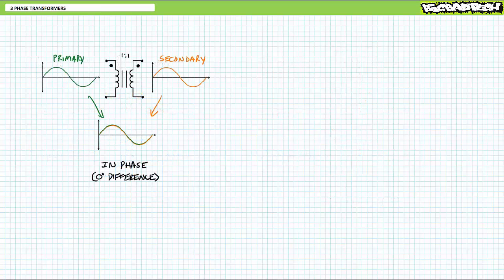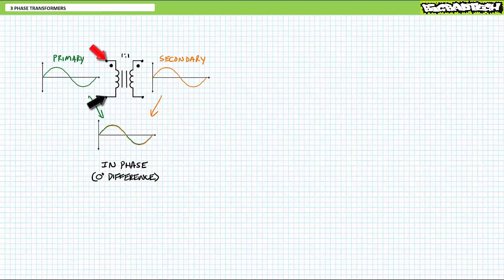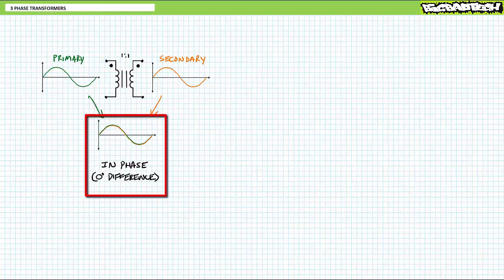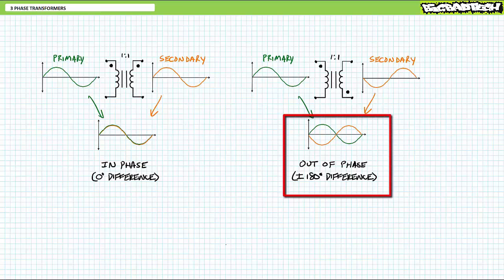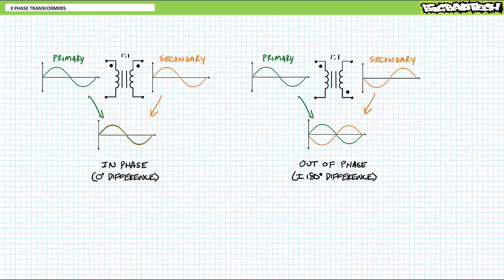Of critical importance for today's discussion on three-phase AC transformers is the location of the phase dots. The ends of the winding with the phase dots simultaneously peak and valley. If we hook up AC voltmeters positive to negative across the primary dotted-end to non-dotted-end and across the secondary dotted-end to non-dotted-end and overlay a plot of instantaneous voltages, we would see the secondary output perfectly in phase with the primary input. However, if the phase dots were on opposite ends of the secondary winding, effectively using the secondary output backwards or inverted, the secondary output would be perfectly out of phase with the primary input, exhibiting a plus or minus 180-degree shift.